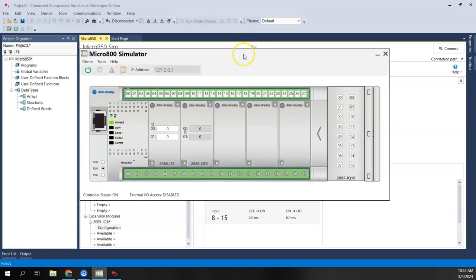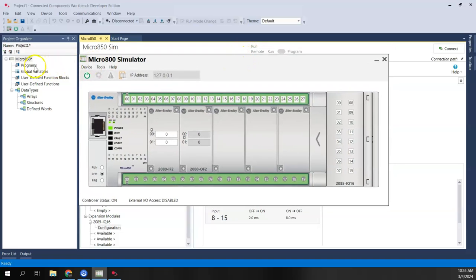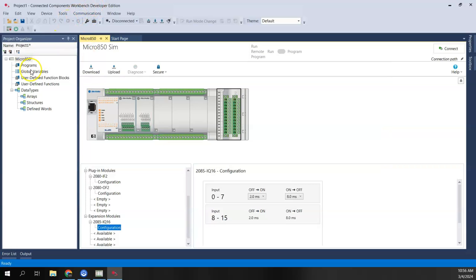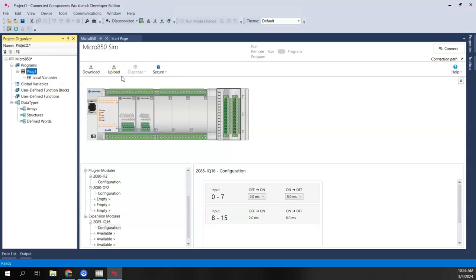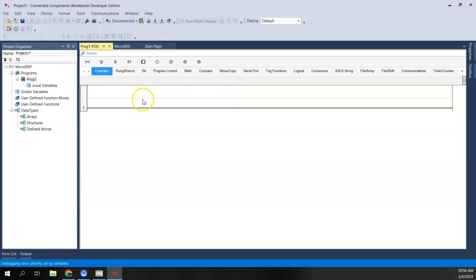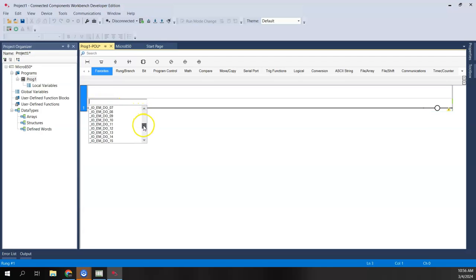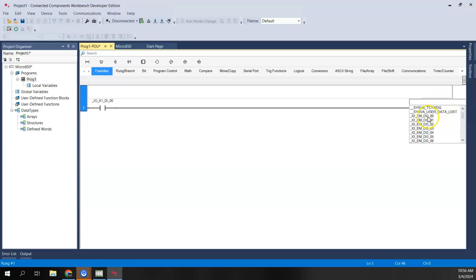Now we can download, but first I want to create at least one simple program to demonstrate the virtual wiring concept. I'll add a ladder diagram with a simple rung: when I turn on one of the expansion I/O points, it will turn on the first output, which in turn will drive the virtual wire connection back to the input. I'll put a contact and coil — if expansion input di00 is on, it turns on embedded discrete output do00.